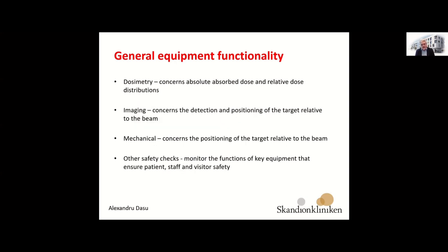In general, if you are going to work or if you are already working in one of these fields, you have to look at the one that is particularly relevant for you. However, there is a red thread through all of them. With respect to general equipment functionality, they recommend to check the dosimetry, the imaging, the mechanical, and other safety checks. Dosimetry is that part of functionality which concerns the absolute absorbed dose and the relative dose distribution that are delivered by the machine. Imaging concerns the detection and the positioning of the target relative to the treatment beam. Mechanical concerns the positioning of the target relative to the beam. Usually, imaging and mechanical are considered together, although imaging, as you are going to see, goes a little bit further than the actual imaging for treatment delivery.